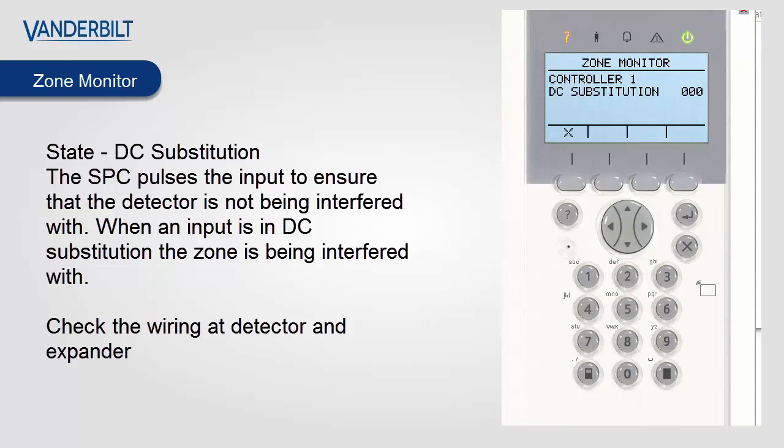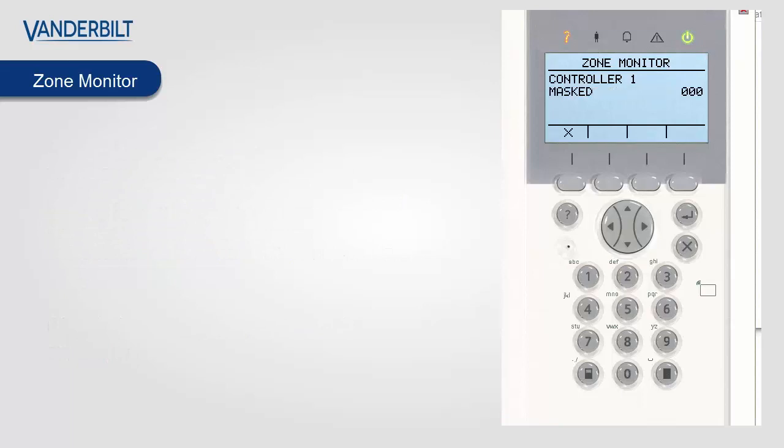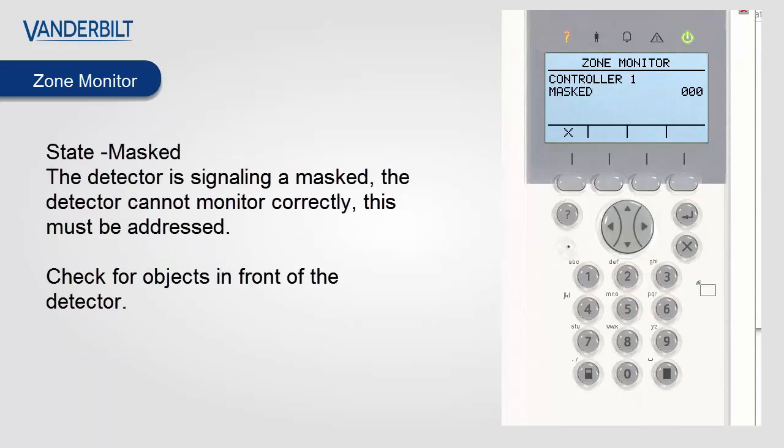State DC substitution: the SPC pulses the input to ensure the detector is not being interfered with. When an input is a DC substitution, the zone is being interfered with and replaced with a DC source. Please check the wiring of the zone to identify this interference. Zone state mask: the detector is signalling a mask condition, meaning the detector cannot monitor the situation correctly and this must be addressed. Check for objects in front of the detector and remove them in order to reset the mask condition.